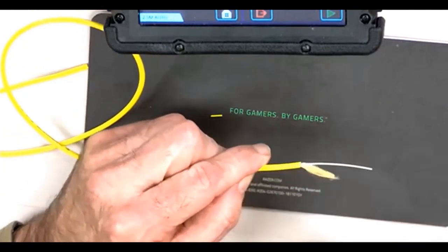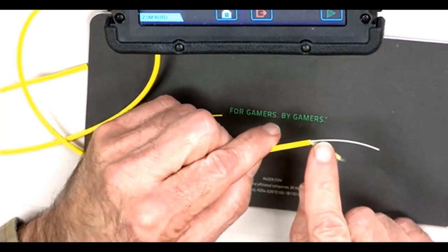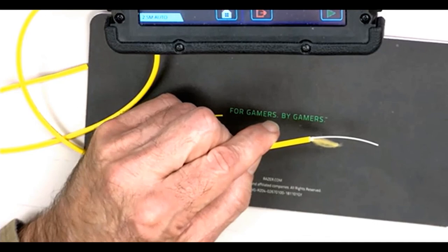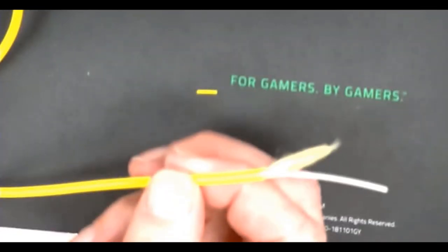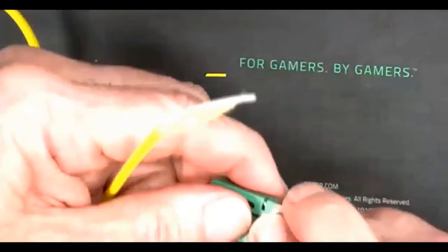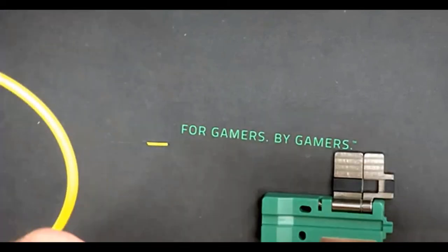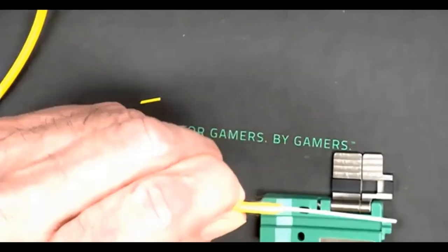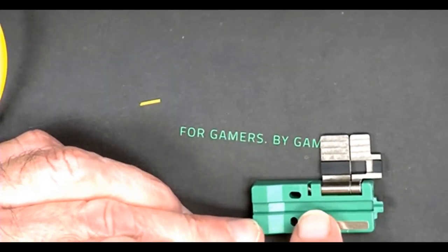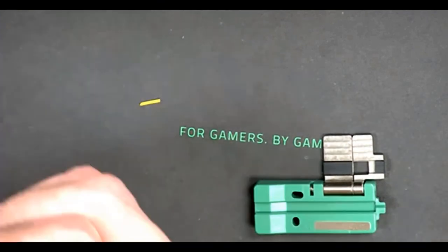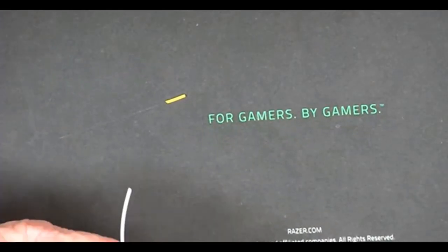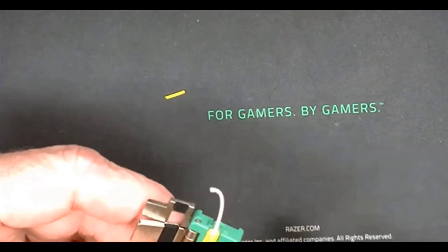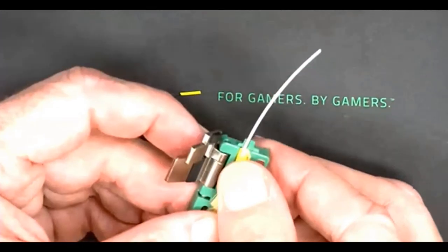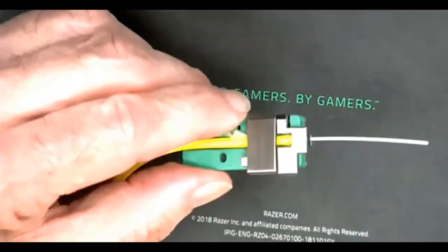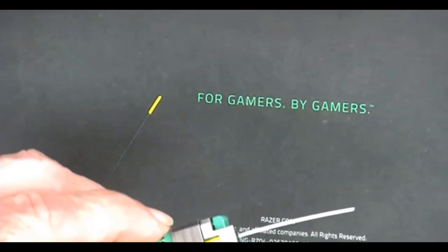And this isn't exactly that length. So here's your 900 micron. You cut this back 32 millimeters. That leaves 3 millimeters here. And then you have to use a special fiber holder, and you fold the Kevlar back. And again, I'm going to want my 900 micron down. The 900 micron goes in this little groove, and all the Kevlar and 3 millimeter goes in there. And then close the clamps. I haven't stripped this, but after this, the process is about the same.